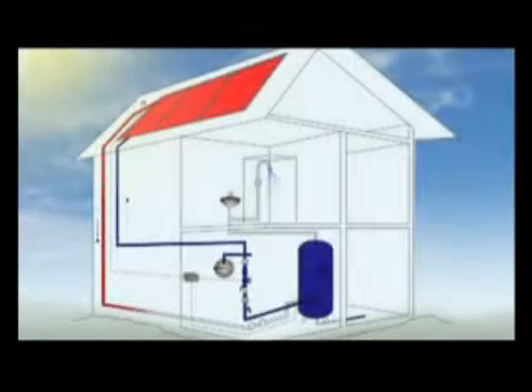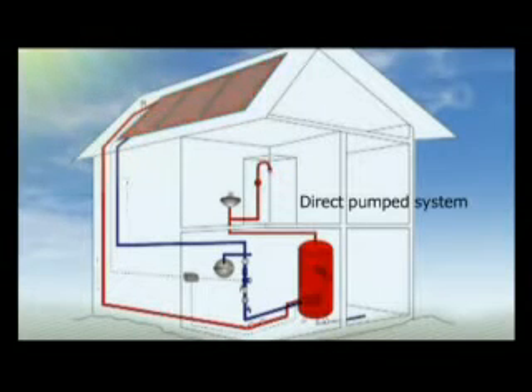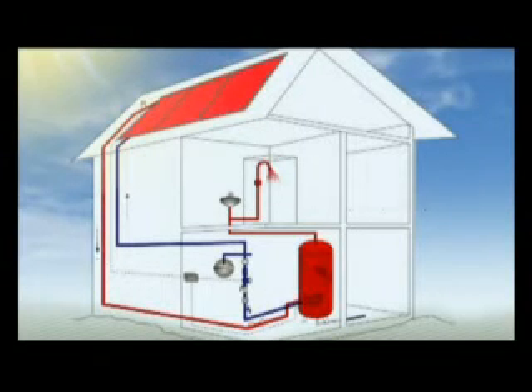Another form of freeze protection in a direct pump system is the recirculation system, whereby the differential controller senses the low temperature of the collector and switches the pump on and circulates the warm water from the tank to the collector to prevent freezing.